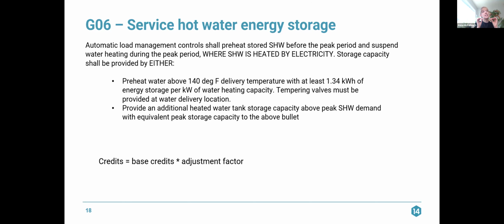And then the second option is to provide an additional heated water tank storage capacity above the peak service hot water demand with an equivalent peak storage capacity to the above bullet, so that 1.34 kilowatt hours of energy storage per kW of peak water heating capacity. The credits available are the base credits times an adjustment factor.